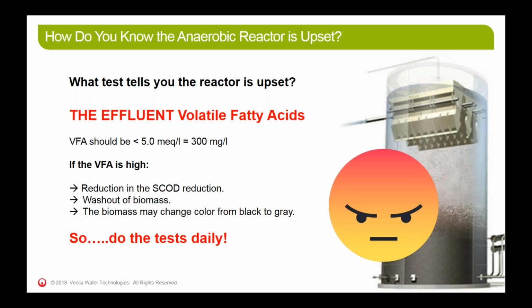Typically, we like to say that if the system has less than 5 milliequivalents per liter of VFA, then the system is relatively stable. If the VFA gets higher than 5 milliequivalents, some different things that you can look at doing is reducing this SCOD load. You could have a washout of biomass. You might see your biomass start to turn color, if it's a blackish color, turn to gray. So it's important that you do the VFA. If you do only one test, and you should be doing more, as Jill told you, make sure you do that VFA test daily.